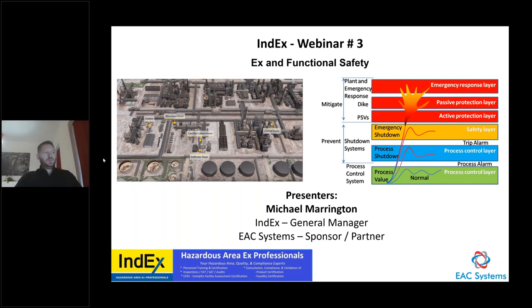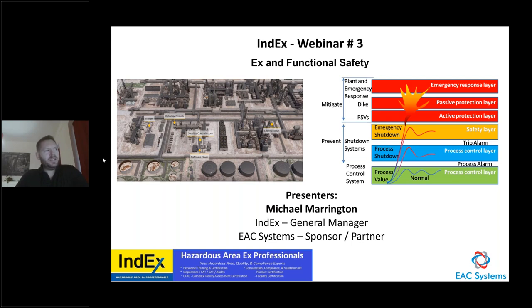When we talk about functional safety, we're talking about different layers of protection. A simple explanation: we have a process control layer for process values, a process control layer for process shutdown when we receive a trip alarm, then we have our shutdown systems. Those are our prevention systems. Under mitigation systems we have pressure relief valves and pressure shutdown valves. For passive protection we have dykes — bunding around an oil tank. That's a passive layer of protection, and then we have plant and emergency response — your firefighting team system, your SIS safety instrument system with a backup system.